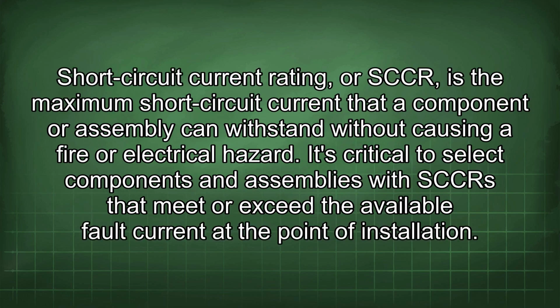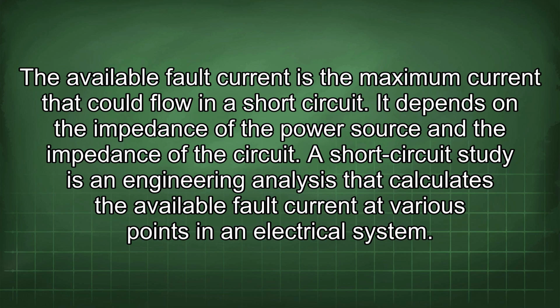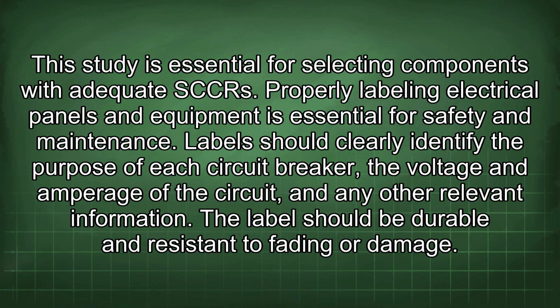Short circuit current rating, or SCCR, is the maximum short circuit current that a component or assembly can withstand without causing a fire or electrical hazard. It's critical to select components and assemblies with SCCRs that meet or exceed the available fault current at the point of installation. The available fault current is the maximum current that could flow in a short circuit. It depends on the impedance of the power source and the impedance of the circuit. A short circuit study is an engineering analysis that calculates the available fault current at various points in an electrical system. This study is essential for selecting components with adequate SCCRs.